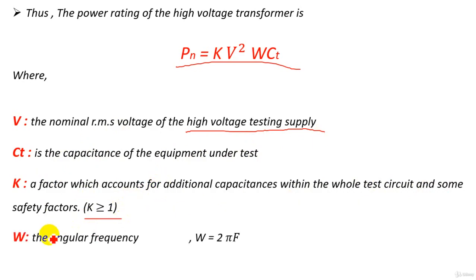Also, we have omega is the angular frequency, while omega equals 2 pi f, and f is the frequency of the supply, which is 50 hertz or 60 hertz. As our transformer produce a high voltage AC but at power frequency as explained before. So this is a complete understanding for our high voltage testing transformer and how this transformer can be used in the lab to produce very high voltage AC at power frequency.